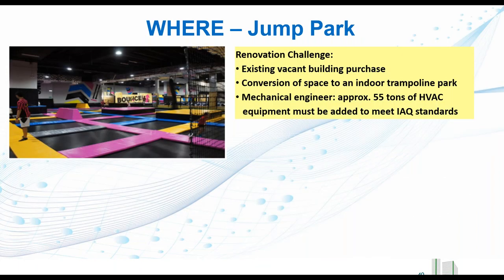Let's look at a jump park. The client was purchasing an existing vacant building, previously had a different occupancy, so it was a conversion of the space to the trampoline park. The mechanical engineering firm came back to the client and shared with them, in order to meet the IAQ standards, an additional 55 tons of HVAC equipment needed to be added.